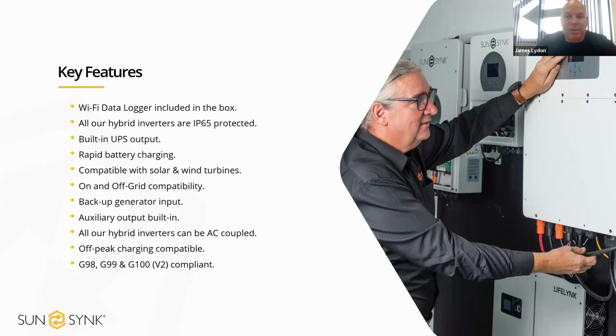But with us, it might only be on 25% of the time because, like I say, while it is on, it's powering the load and charging the batteries. One thing we always recommend with backup generators is to always size it a minimum of 150% larger than the size of the inverter.